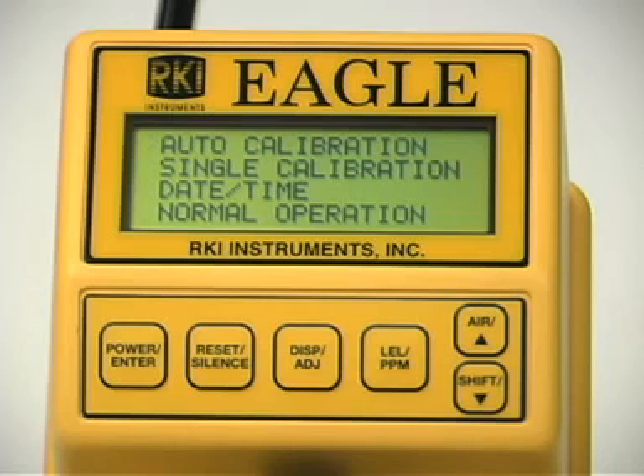The Eagle's calibration menu includes two methods of calibration: auto calibration and single calibration. Auto calibration allows you to calibrate all four sensors simultaneously. It is designed for use with the RKI 4-gas calibration cylinder and is the quickest and easiest method to calibrate the Eagle. Single calibration allows you to calibrate one sensor at a time. Use this method if you are only calibrating one or two sensors, or if you are calibrating non-standard toxic sensors, or if you're not using the RKI 4-in-1 calibration cylinder.